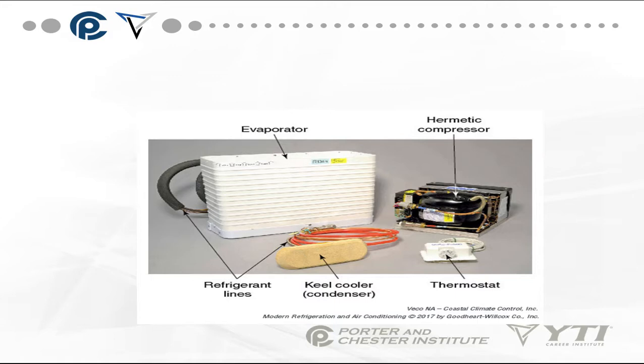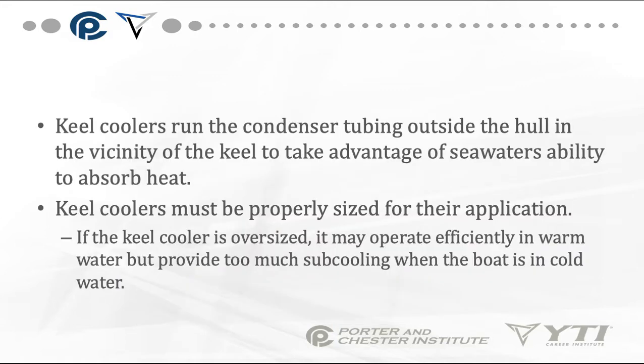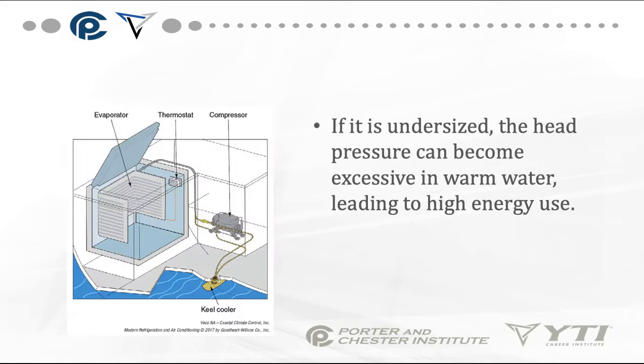This is an example of a full marine refrigeration system, showing the hermetic compressor, the evaporator, and a keel cooler condenser, where the refrigerant lines actually go through the hull. Keel coolers run the condenser tubing outside the hull near the keel to take advantage of seawater's ability to absorb heat. Keel coolers must be properly sized — if oversized, the system may operate efficiently in warm water but provide too much subcooling in cold water; if undersized, head pressure can become excessive in warm water, leading to high energy use.